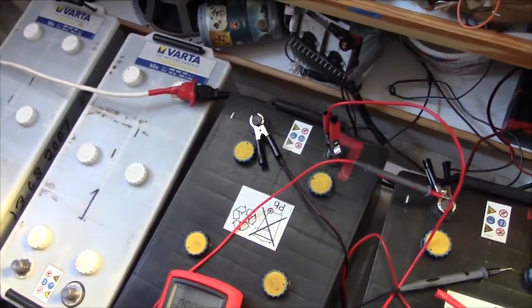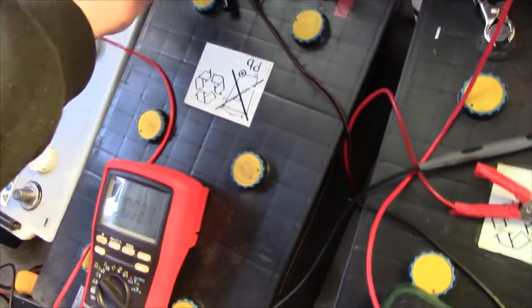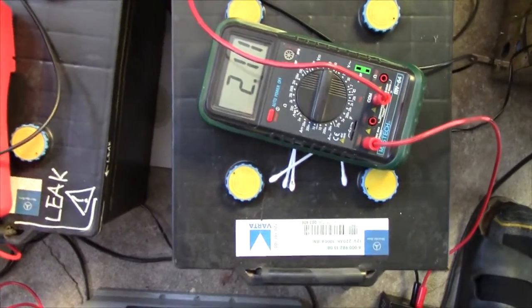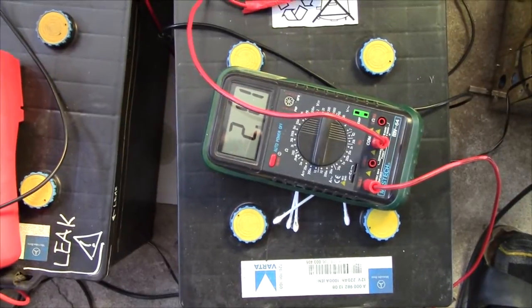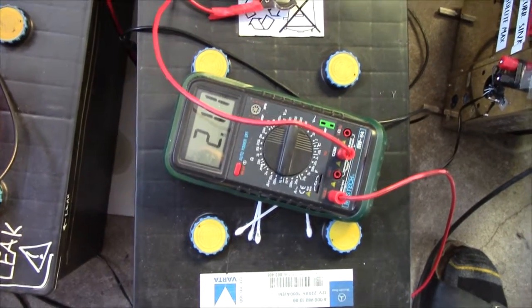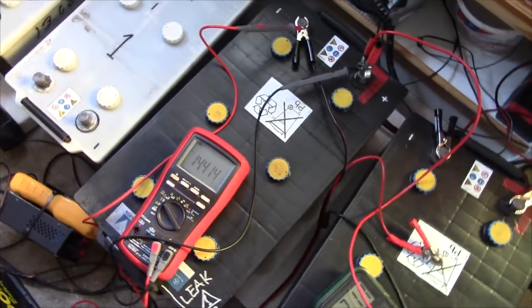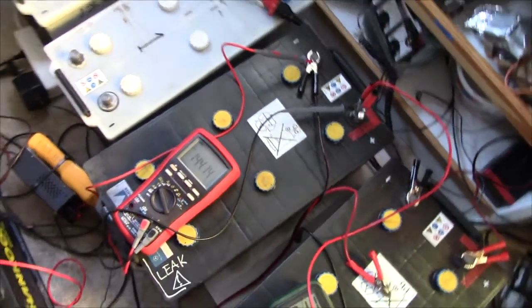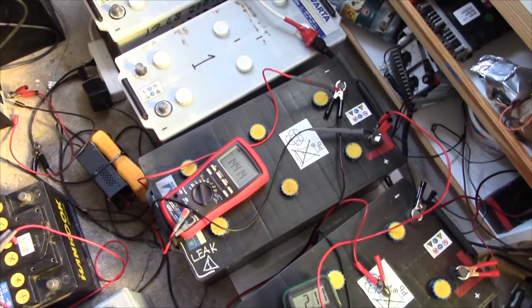As for the less fortunate battery, it's been charging on the 7 amp chargers, just one of them overnight. And it's down to just over 2 amps. For a 220 amp hours rated battery, that's a pretty good full charge. I'm going to drop that one down to float charging and maybe do a cycle on it tomorrow. Well, no, actually I'm going to equalize this one today. That's what I'm going to do. Time to just hook up my load and see what happens.